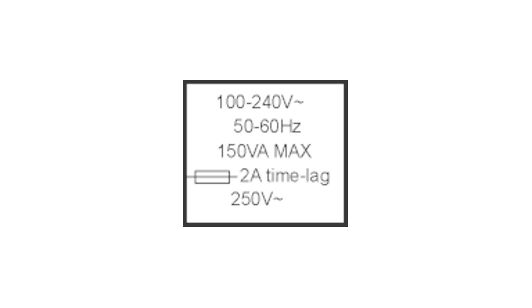To minimize these risks, make sure that you are using properly rated equipment and inspect for damage regularly. It is also very important to have a fire extinguishing device near the laser equipment. Whether a fixed or handheld device, be sure that it has the correct rating and is properly sized to do the task at hand. Asphyxiation and chemical hazards.